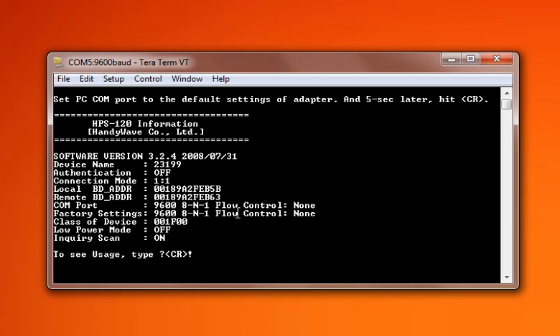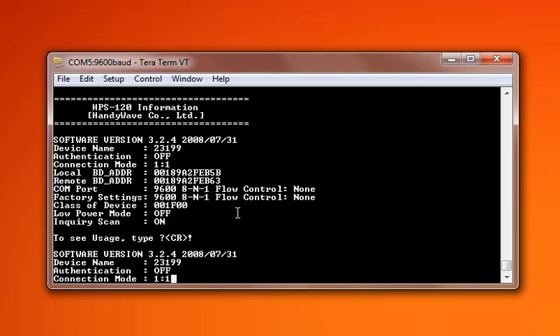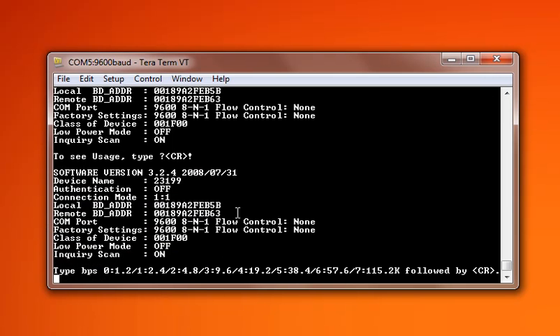Now, say we have a device which transmits at 19,200 bits per second. It's a very common request to have the unit change to that baud rate. So for that, all we do is follow the manual that mentions an uppercase B.